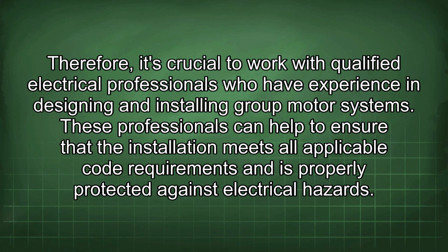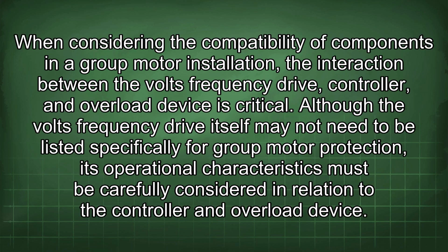protected against electrical hazards. When considering the compatibility of components in a group motor installation, the interaction between the volt-frequency drive controller and overload device is critical. Although the volts-frequency drive itself may not need to be listed specifically for group motor protection, its operational characteristics must be carefully considered in relation to the controller and overload device.